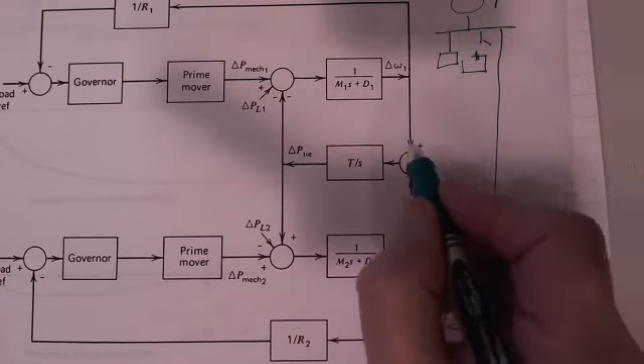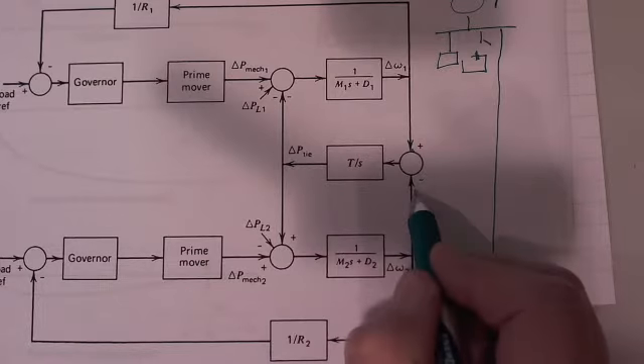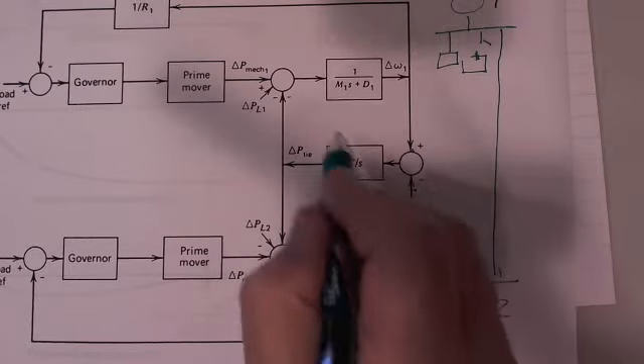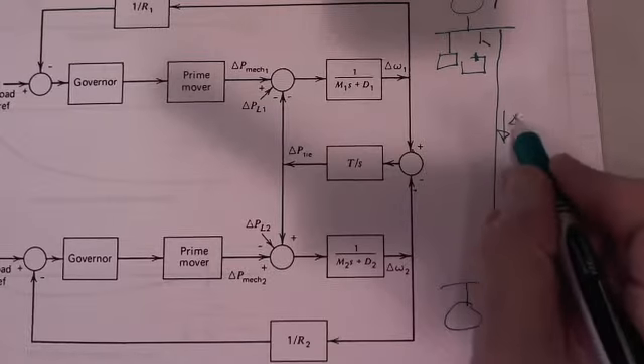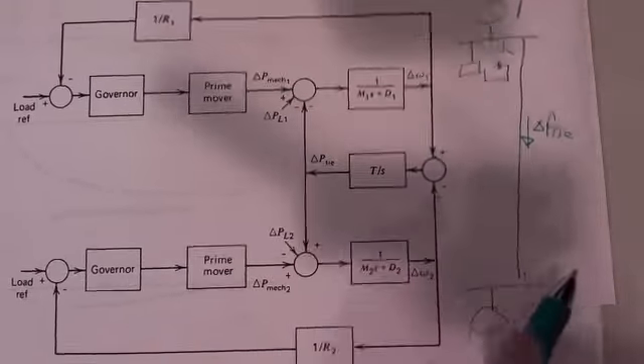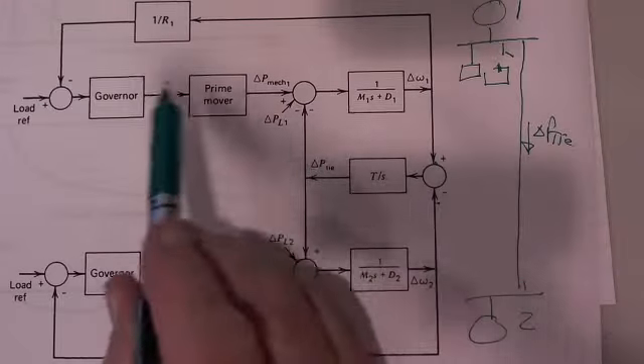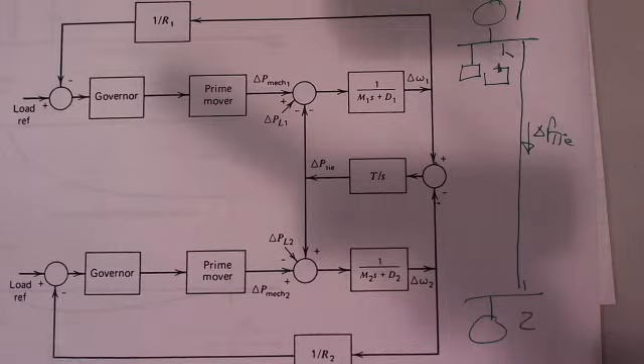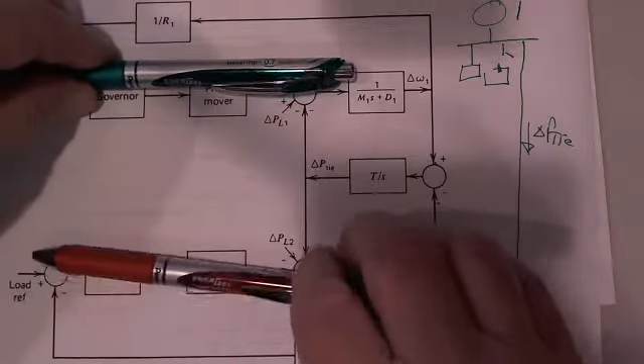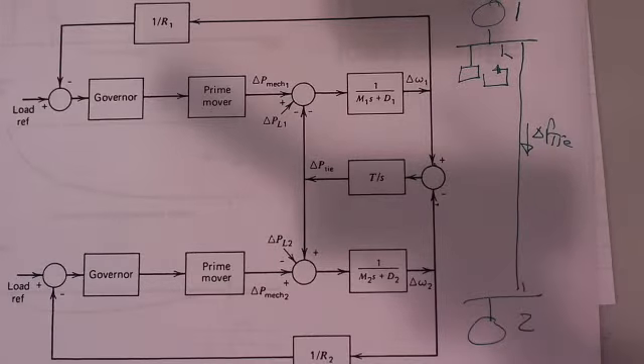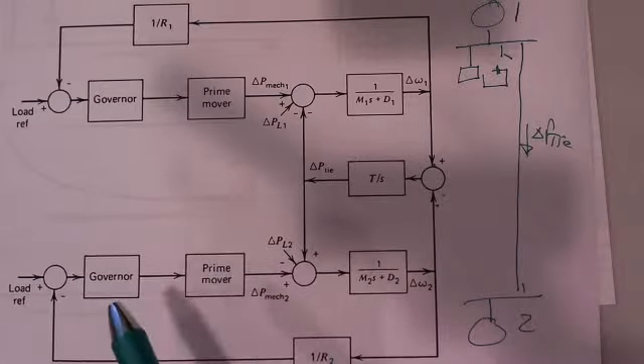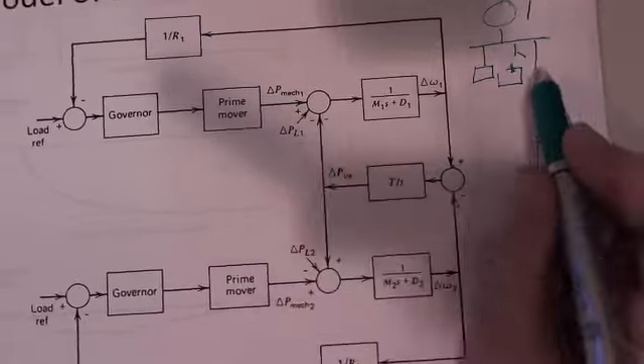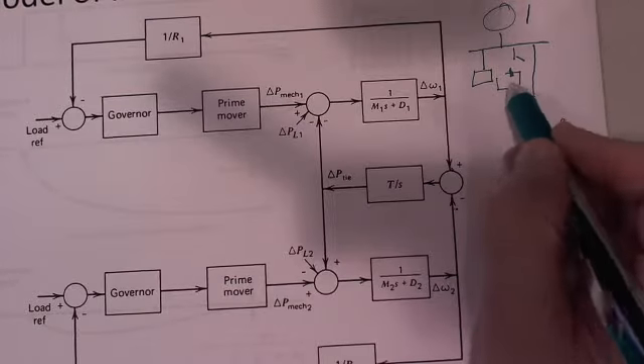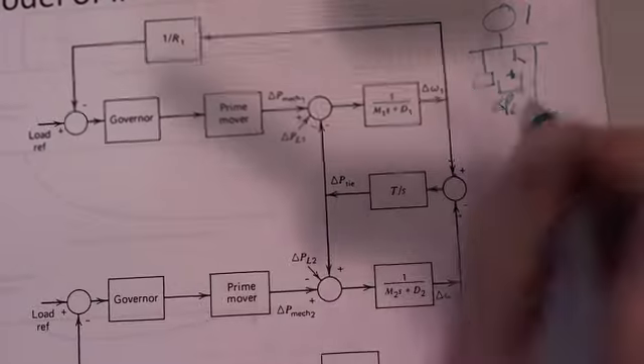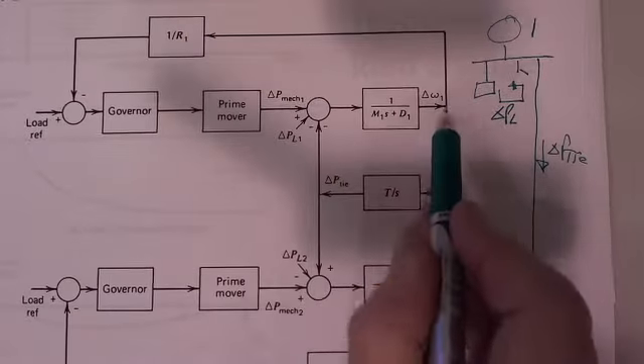By integrating the difference of delta omega 1 and delta omega 2, there's the T over s, I get the change in flow, delta P tie line. I have two identical models here, except for maybe some of the parameter values, but they're identical models of generators. They each have a load reference point, and here's this little delta P load, which is the change of this switch here. So I get delta PL up here, and the delta omega comes out.